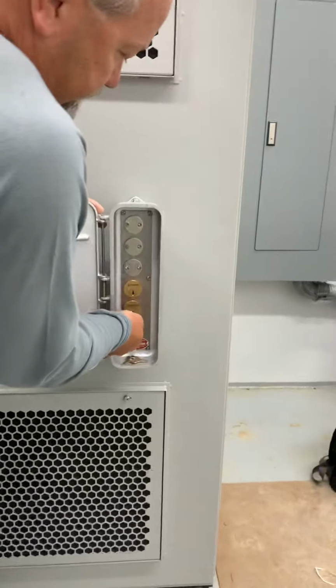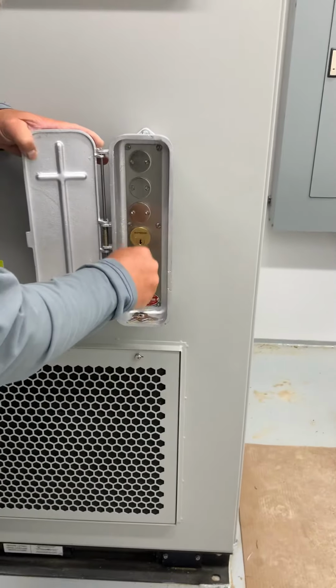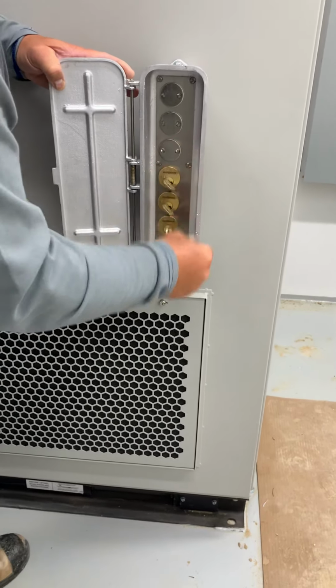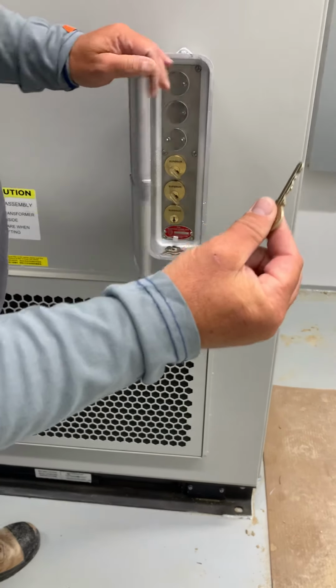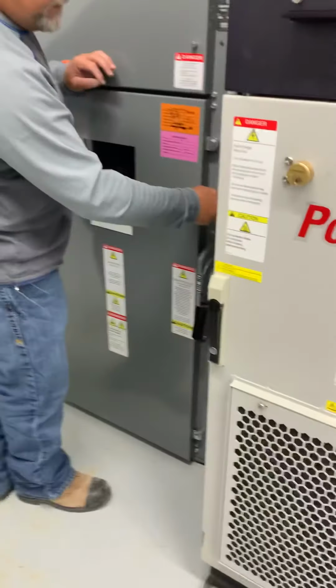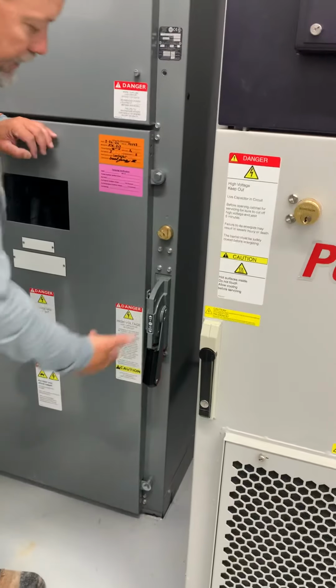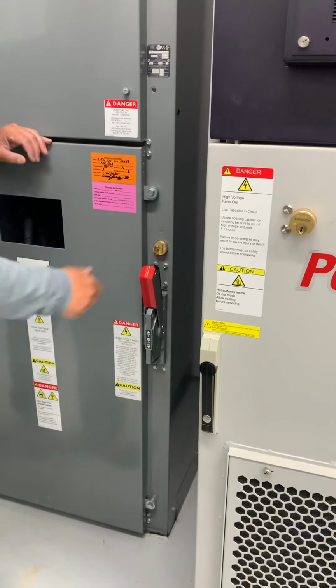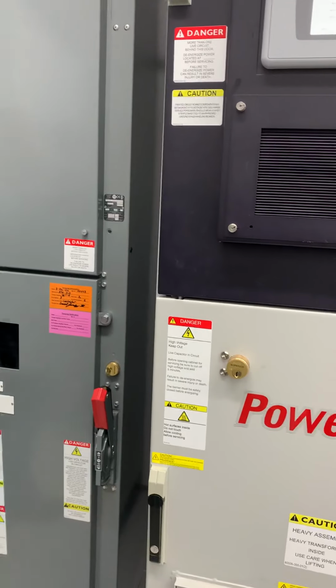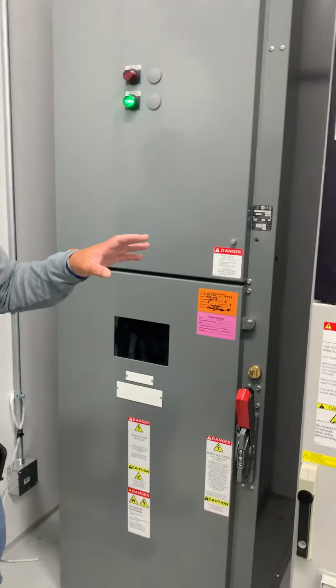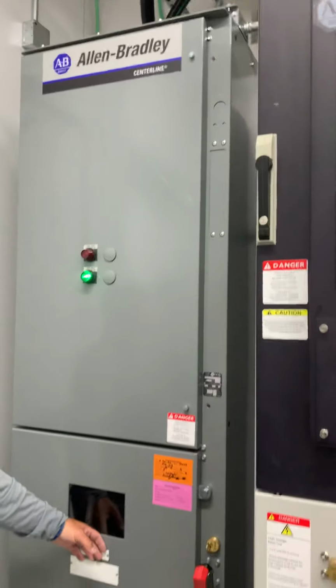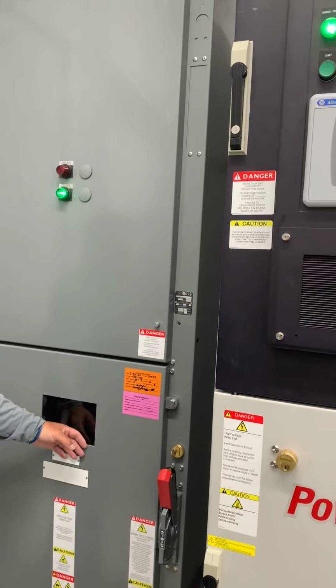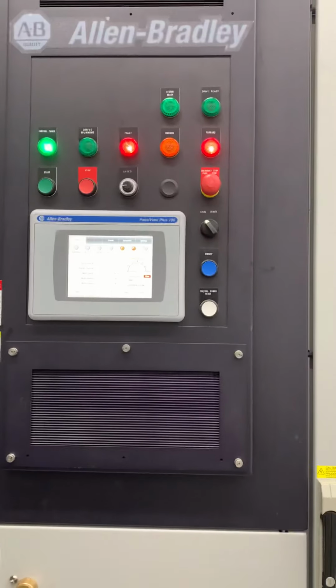In order to turn that back on, we have to return the keys over here to the box, and then take the main key out, put it in the disconnect, turn it, and turn this back on. Now you've got medium voltage going to the drive. It's not powering up the drive yet because you don't have it going to the drive, you have it going to the contactor. Gotcha. So when you pull the E-stop, the contactor will go in.